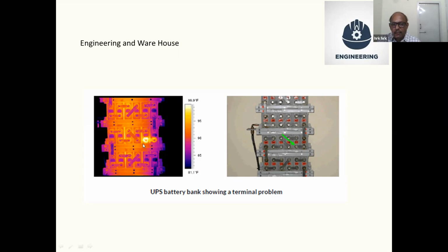These hotspots in batteries we can find out using thermography equipment, which shows the exact temperature of the terminals. If all other things are normal and only one battery terminal is hot, this we call a hotspot, and we take corrective action.